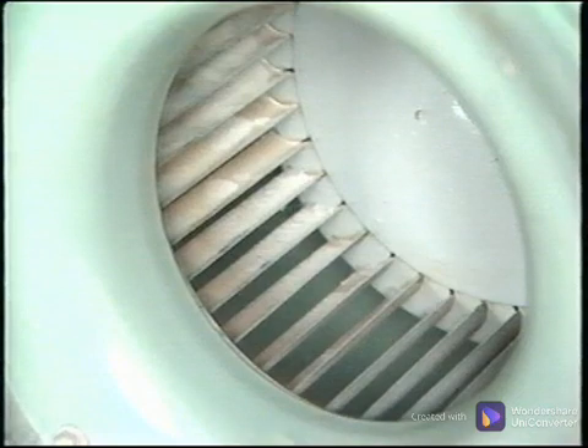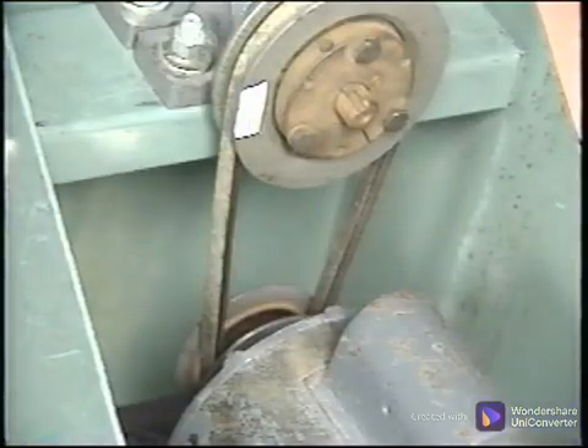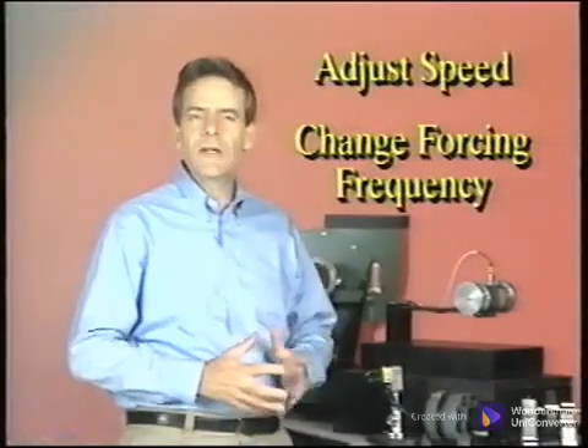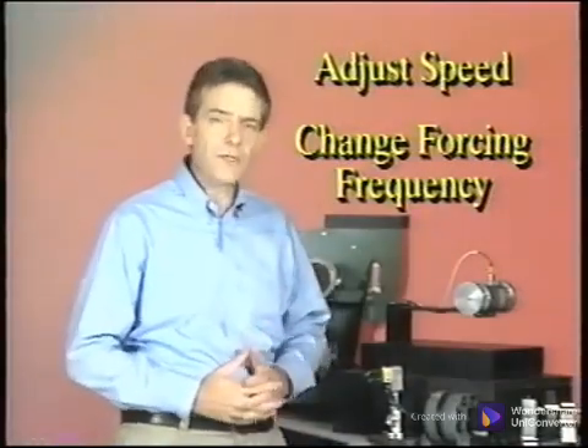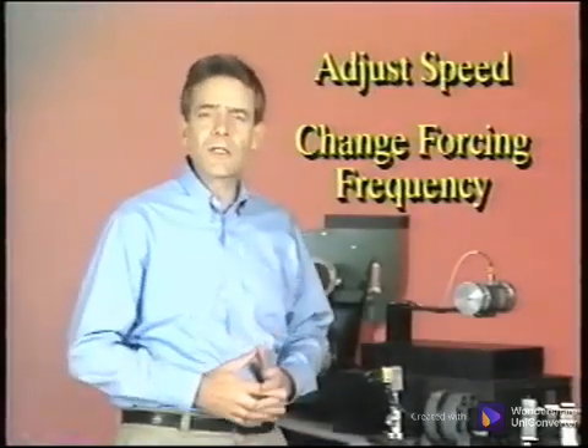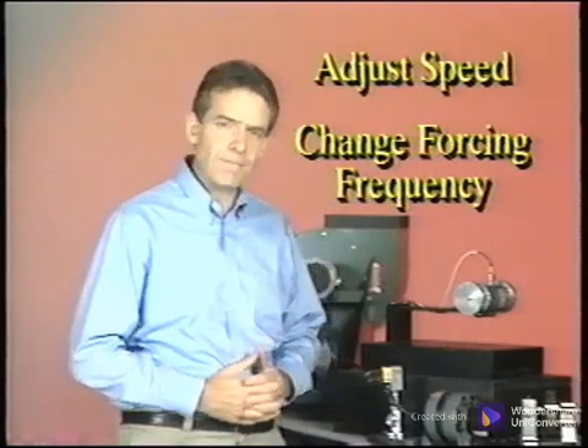If resonance on a fan is at blade pass frequency, change the number of blades on the fan. If the resonance is equal to the frequency generated by a coupling, change the coupling type. If the resonance is a multiple of the belt frequency, change the sheave size or belt type. Adjusting the machine speed or changing the forcing frequency are the two simplest methods to correct a resonance problem.